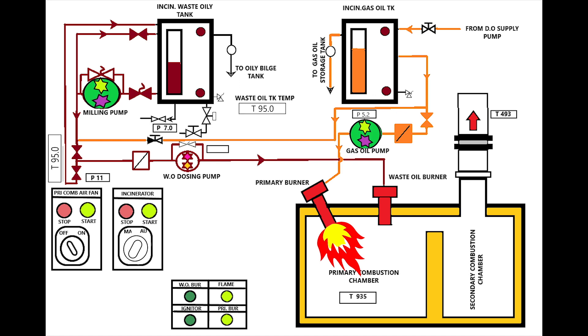Meanwhile as the temperature inside the chamber reaches above 650 degree celsius, switch on the sludge mode and operate the waste oil dosing pump.